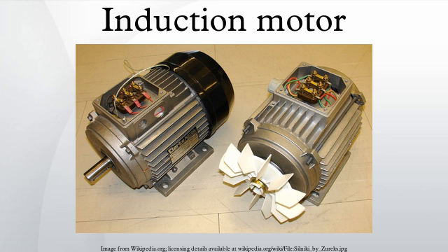Polyphase motors have rotor bars shaped to give different speed-torque characteristics. The current distribution within the rotor bars varies depending on the frequency of the induced current. At standstill, the rotor current is the same frequency as the stator current, and tends to travel at the outermost parts of the cage rotor bars. The different bar shapes can give usefully different speed-torque characteristics as well as some control over the inrush current at startup. In wound rotor motors, rotor circuit connection through slip rings to external resistances allows change of speed-torque characteristics for acceleration control and speed control purposes.